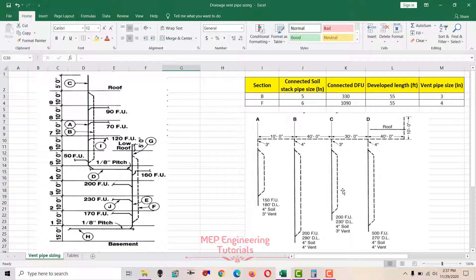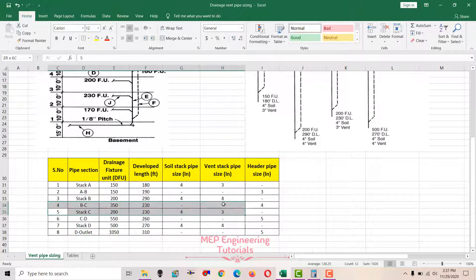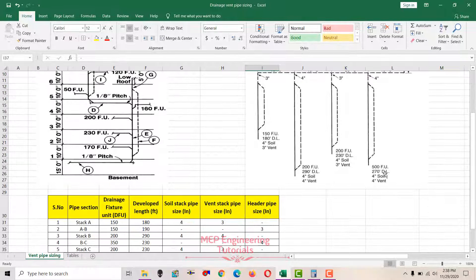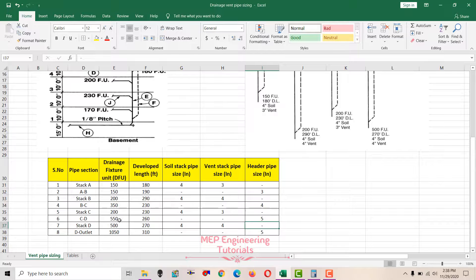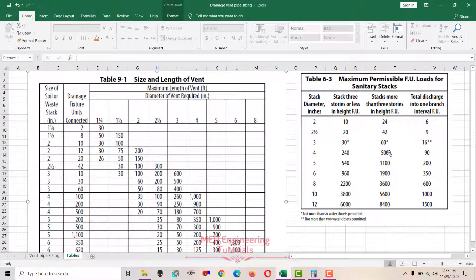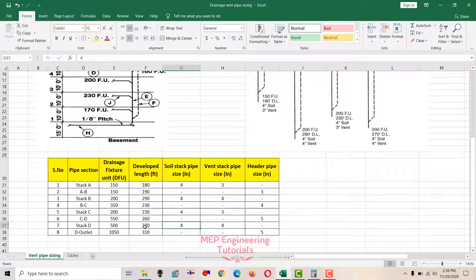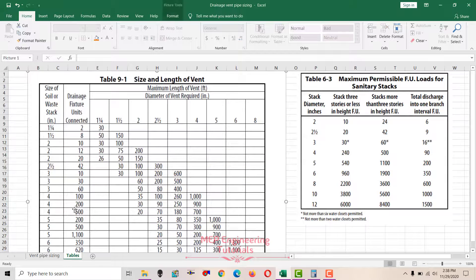Skipping the C and stack C calculations to save time, we go directly to stack D: 500 fixture units and 270 feet developed length. Using Table 6-3, soil stack pipe size is 4 inches. Using Table 9-1 with 4-inch soil stack, 500 fixture units, and developed length 270 (between 180 and 700, go to 700) — the vent stack pipe size for stack D is 4 inches.